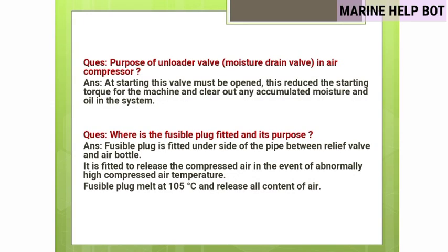The purpose of the unloader valve and moisture drain valve: at starting, this valve must be opened to reduce starting torque for the machine and to clear any accumulated moisture and oil in the system. Reducing starting torque prevents motor overloading and potential burning.